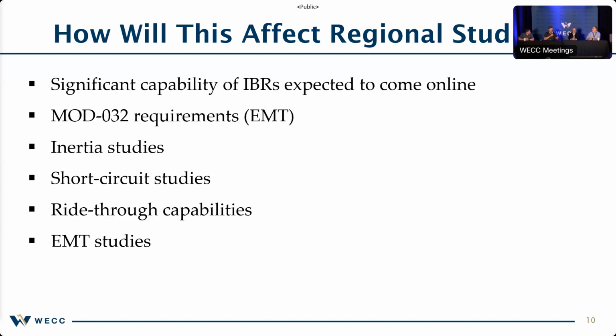So identifying faults, tripping, grounded lines, those kinds of things become more difficult. There's work going on to identify how we can best mitigate that and make sure it isn't causing protection systems problems. Then ride-through capabilities - you heard Rich talking about momentary cessation. Turns out that's just one of the things IBRs are doing that we maybe don't want them to be doing. Honestly, I feel like this is more because we didn't know what we could get out of IBRs originally - it was, hey, here's the requirements, meet them. I think that was sort of the approach. I think we've discovered, since these are much quicker responding, that there are probably capabilities we can leverage from IBRs that we're not leveraging because we sort of limited them to our traditional view of generators.